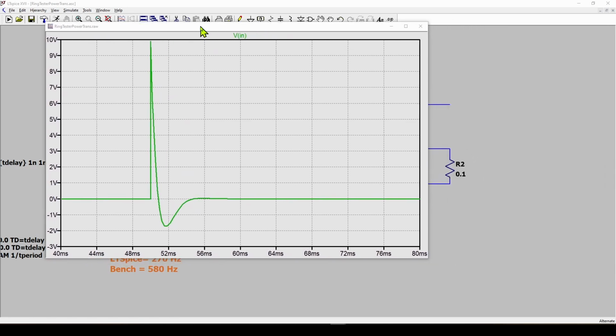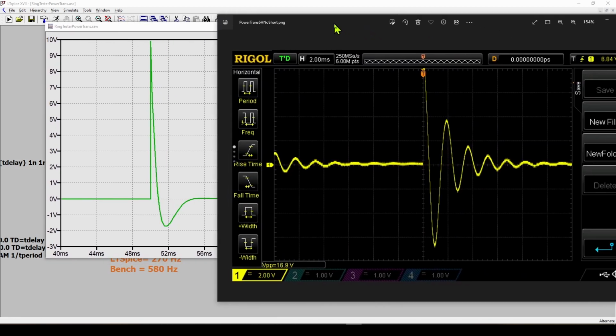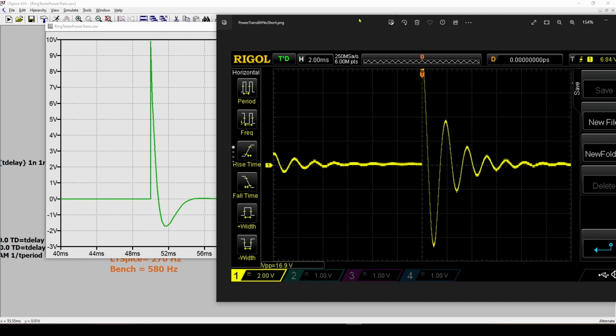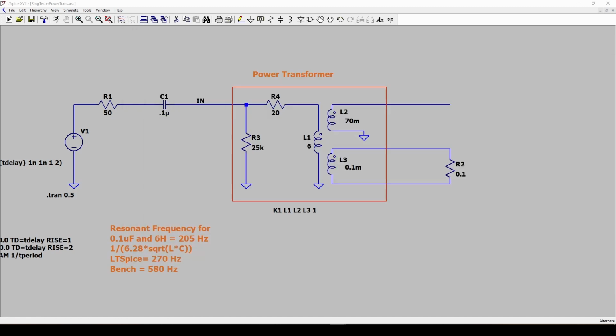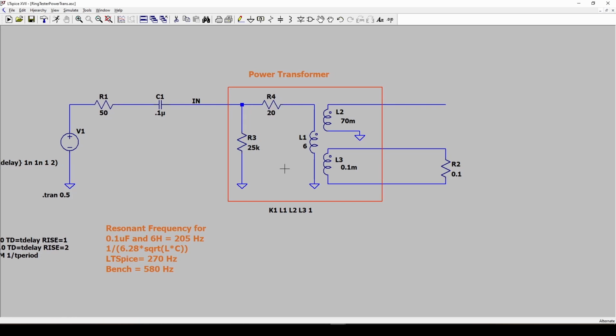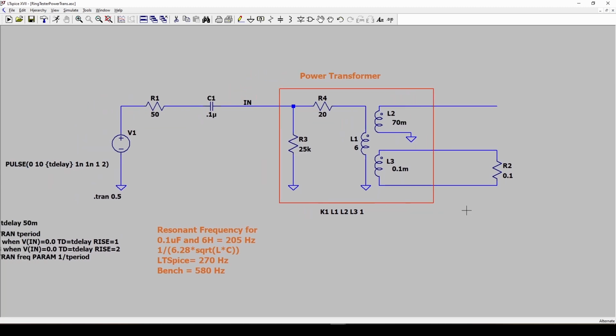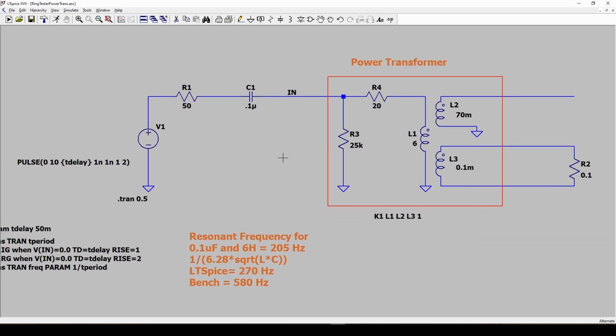So the difference between a shorted turn and an unshorted turn, you know, maybe there's only one ring to determine the difference. And again, I encourage you to look at the previous videos on the ring tester. There's a lot more complications in the ring tester that can affect this, but we can see that different transformers have different characteristics, and in some cases, this resistive core loss may be a factor, with a switching transformer, maybe not. So it really can get very complicated. So just one other example of how a ring tester, unless you really, really know what transformer you've got and what its characteristics are, the results of a ring test may be of little or no use to you.